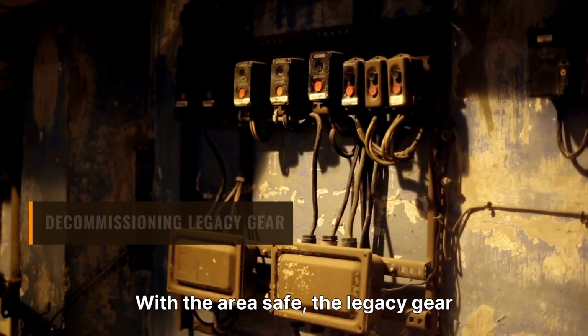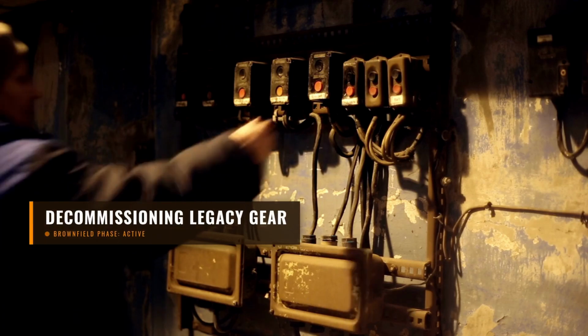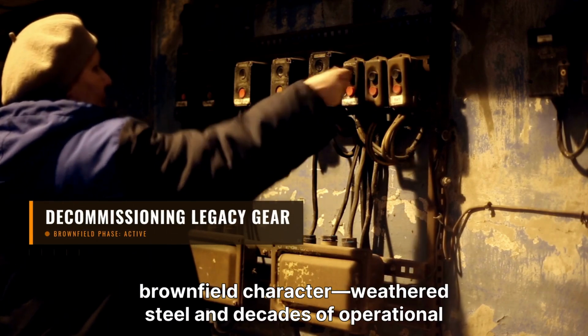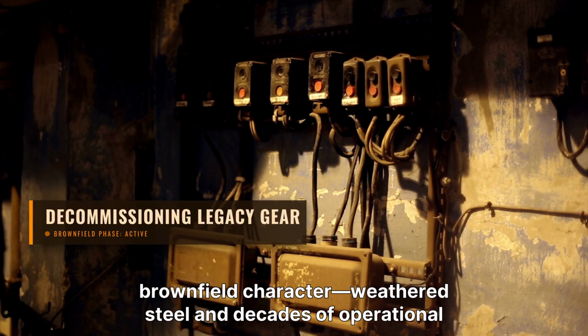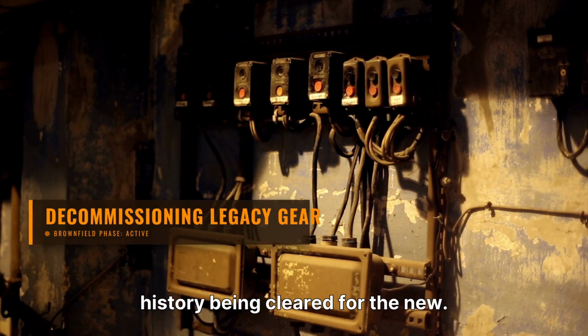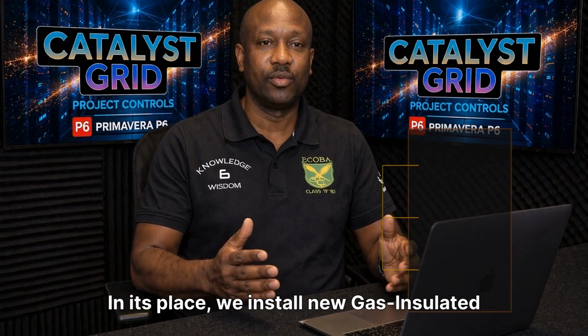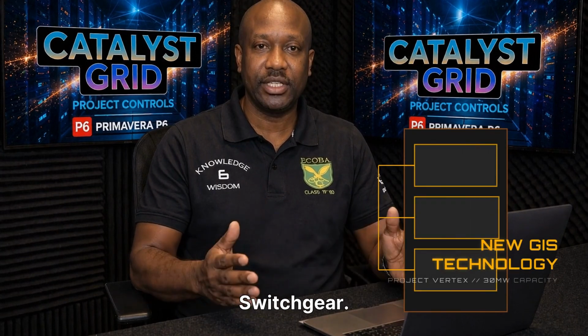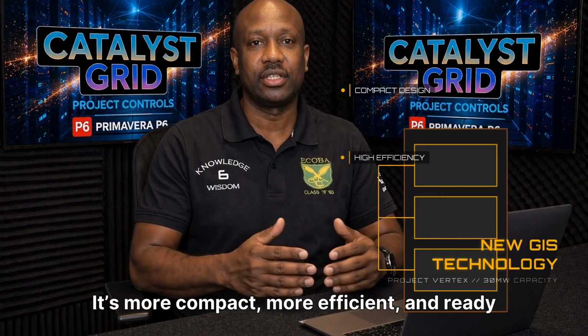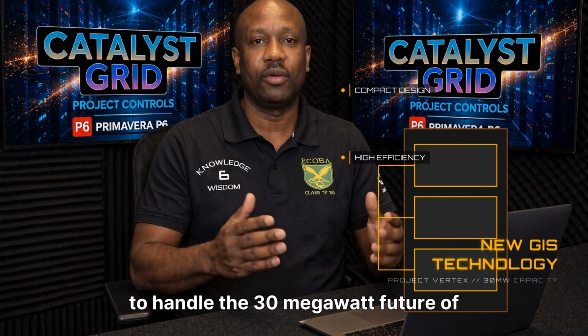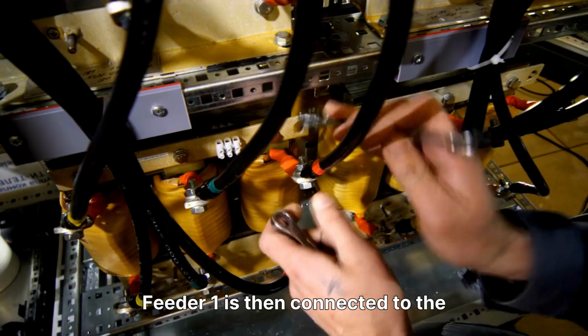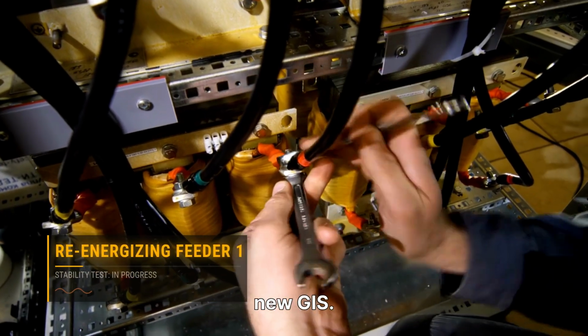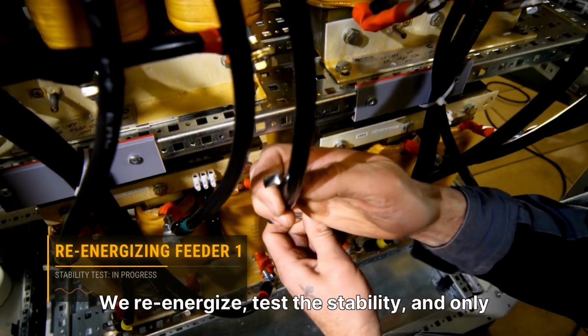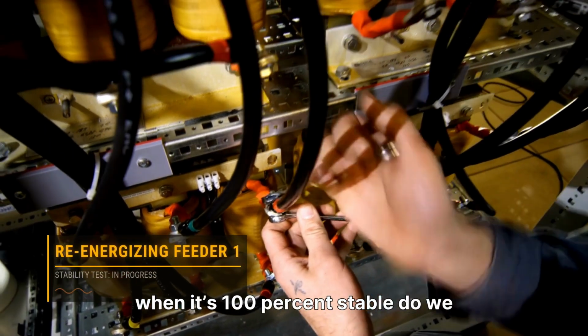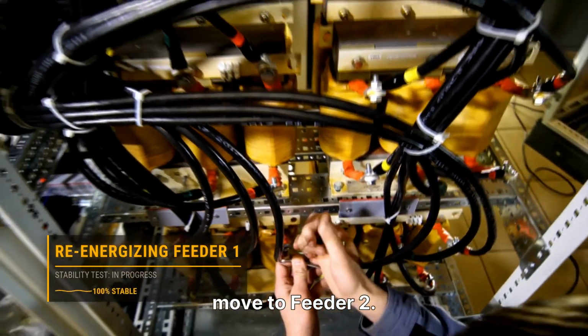With the area safe, the legacy gear is removed. This is where we see the true Brownfield character, weathered steel and decades of operational history being cleared for the new. In its place, we install new gas-insulated switchgear. It's more compact, more efficient, and ready to handle the 30-megawatt future of Project VERTEX. Feeder 1 is then connected to the new GIS. We re-energize, test the stability, and only when it's 100% stable do we move to Feeder 2.